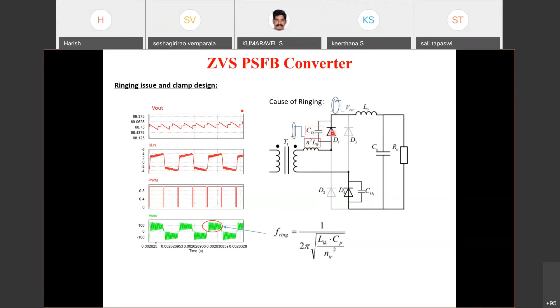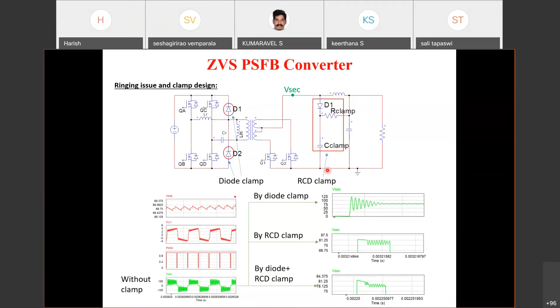There are multiple ways of solving this. One is adding clamp diodes on the primary side, and another is adding an RCD clamp on the secondary side. With just a diode clamp, the system is much better than without any clamp — the ringing ends after just a few cycles, but that's probably not good enough. With the RCD clamp, the overshoot is tremendously reduced, and a combination of the two is much better. But the problem with the RCD clamp is that it's lossy, so you have to strike a balance between efficiency and how much ringing you can tolerate. If you have enough capacitance on the secondary side, you may be okay. These are all things you may very well face in an EV charging application.